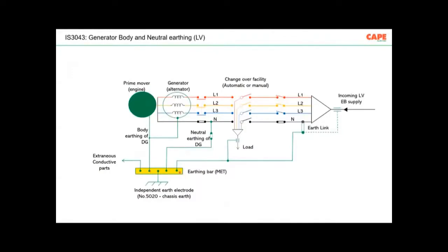How to make an earthing of your DG, for example, in IS 3043, picture 38 to 41, you can find this picture. The only difference is I put it in a color combination, RYB, black for neutral, and green is the earth wire. The DG body, engine and alternator body is connected to earth bus bar. Neutral of the DG is connected to the same bus bar. Incoming EB supply, the PE conductor is connected to the same bus bar. Load side protective earth conductor is connected to the same bus bar. The same bus bar is connected to independent earth electrode with a number 5020. The same bus bar is connected to extraneous conductive parts such as other metallic parts. This is how you are supposed to make an earthing in your installation.